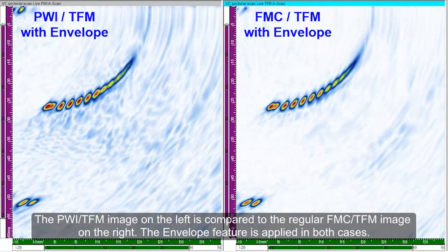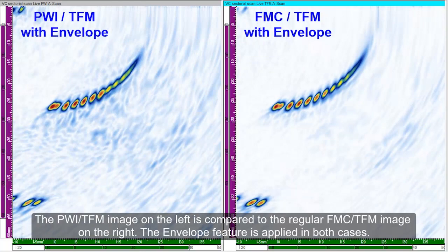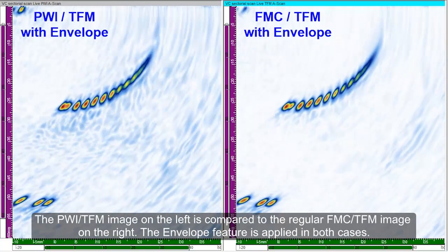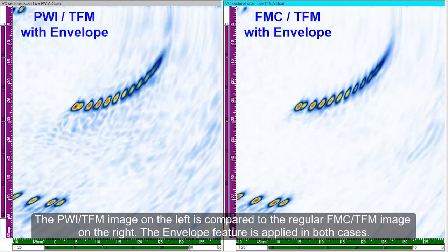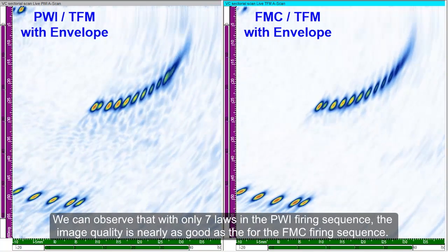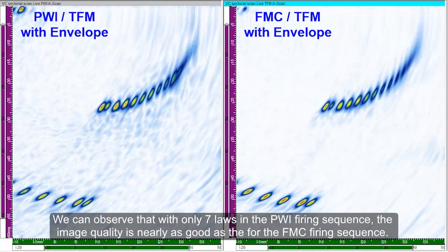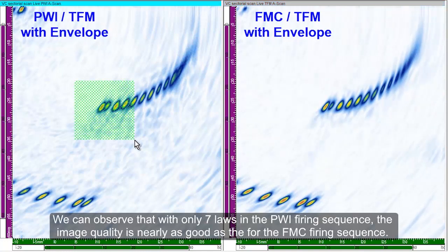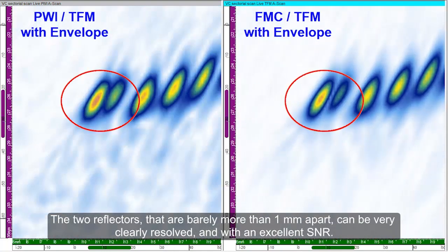The PWI TFM image on the left is compared to the regular FMC TFM image on the right. The envelope feature is applied in both cases. We can observe that with only 7 laws in the PWI firing sequence, the image quality is nearly as good as for the FMC firing sequence. The two reflectors, that are barely more than 1 mm apart, can be clearly resolved with an excellent signal-to-noise ratio.